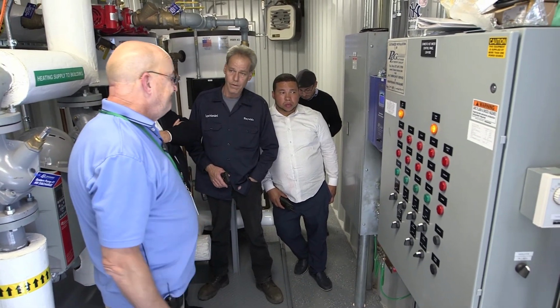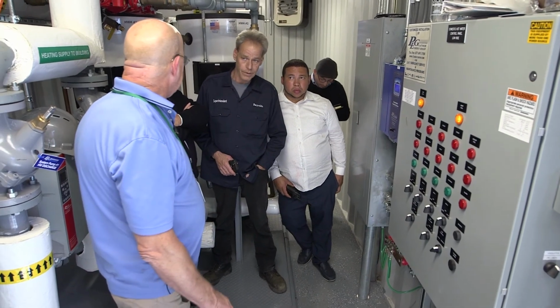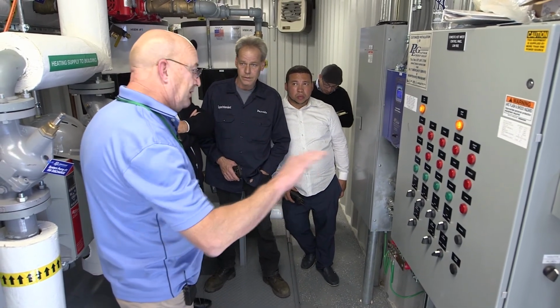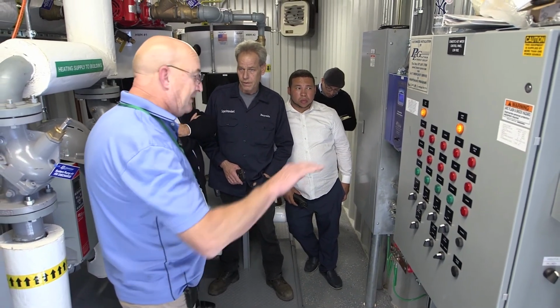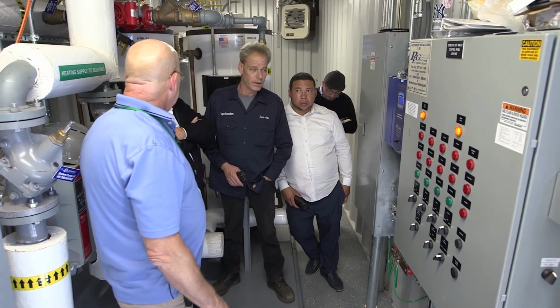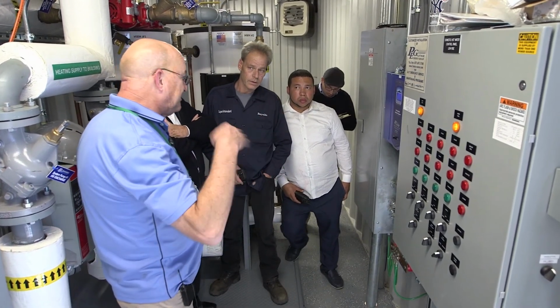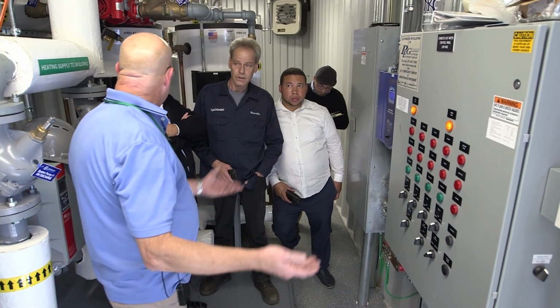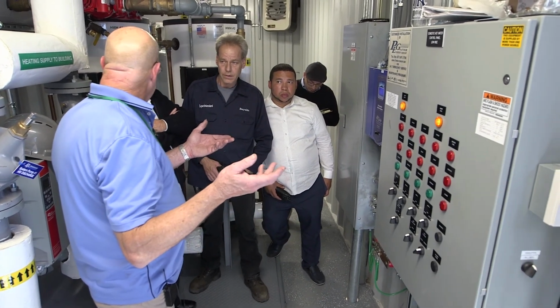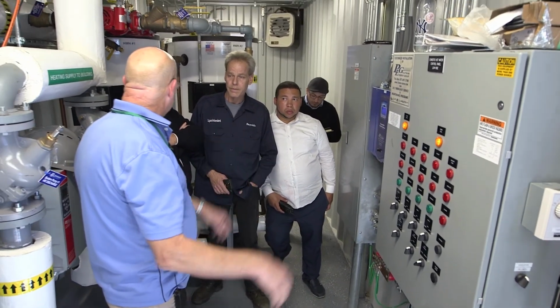You could say, listen, I'm going to give them a little heat. You can click right on the screen and say bypass. You hit bypass. Pretty good. A minute later, you'll see that light flash, bypass boiler's on. You'll actually see the boilers come on, and the lights will light up that the boilers are running and the pumps are running.